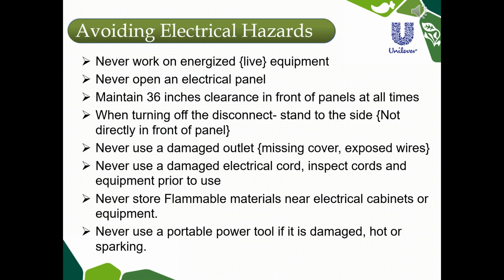So how do you avoid electrical hazards? Never work on energized equipment, live equipment. Never open an electrical panel. Make sure that we maintain a 36-inch clearance in front of all electrical panels at all times. If you're turning off a disconnect on an electrical panel, stand to the side, not directly in front of the panel. Never use a damaged outlet. Never use a damaged electrical cord. You should always inspect your cords and equipment prior to use. Never store flammable materials near electrical cabinets or equipment, and never use a portable power tool if it's damaged, hot, or sparking.